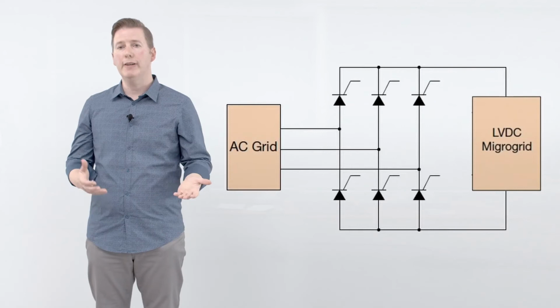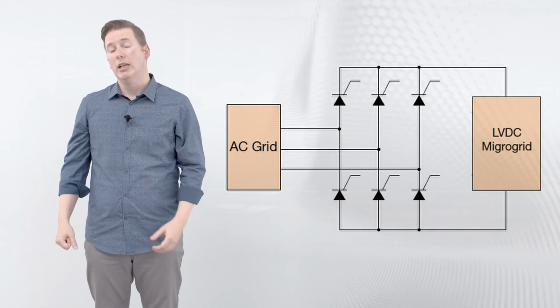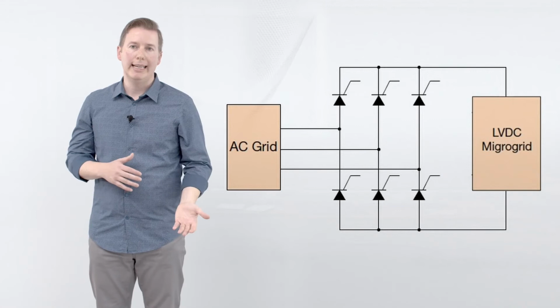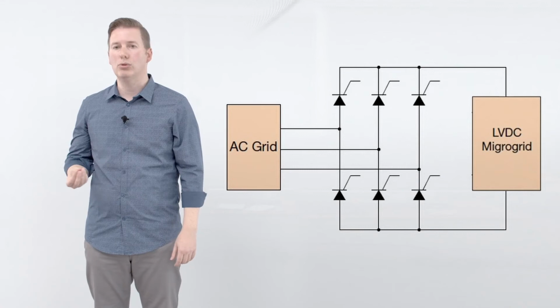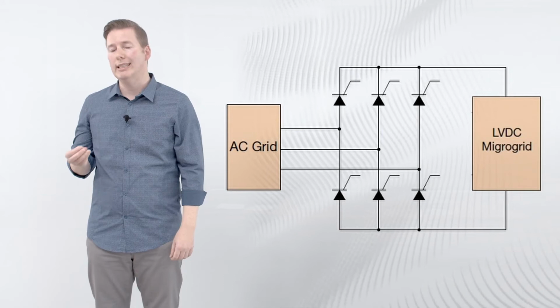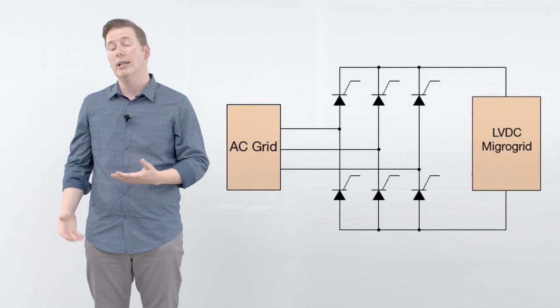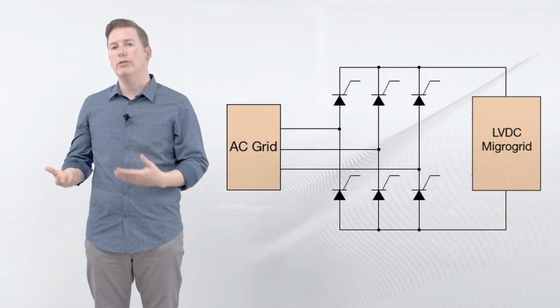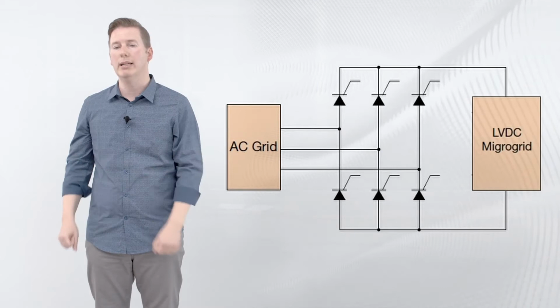As we have seen before in the single line diagram, usually in an EVCI we have both a main AC-DC converter and a lot of DC converters. As you can see here, if the main AC-DC converter is a thyristor rectifier, usually thyristors are able to both limit and interrupt the fault current by not sending the closing command to their gates. Nevertheless, thyristors cannot be used in EVCI with the so-called vehicle-to-grid function, because in case of reversal power, we would have to change the DC voltage direction, with obviously serious problems with the several devices attached.